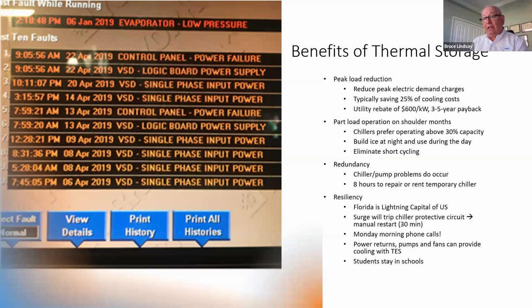What we noted, though, is that the schools that had ice storage systems did not have students leaving. Why is that? Well, because as you have power, you can run your pumps and your fans, and if you got ice sitting back there, you can cool the building. The only problem would be in the afternoon, if you burned all your ice, you might have to turn the chiller on during a peak period and get slammed with a demand charge.